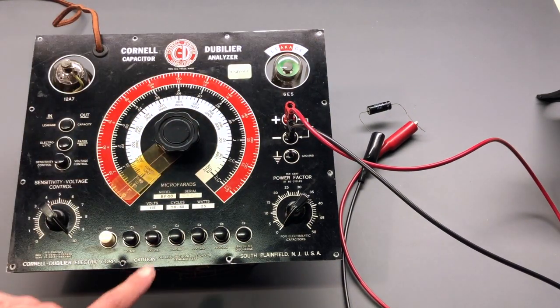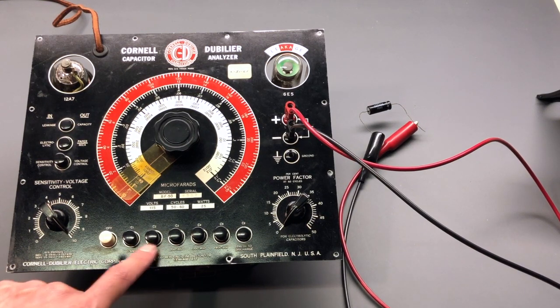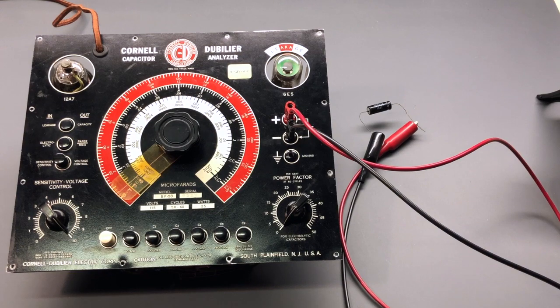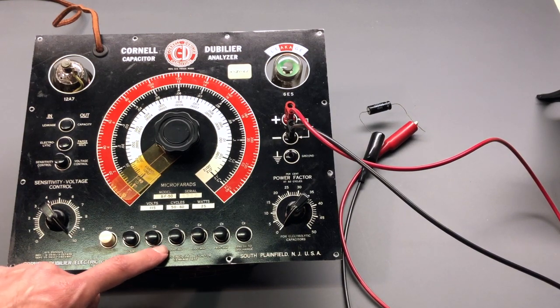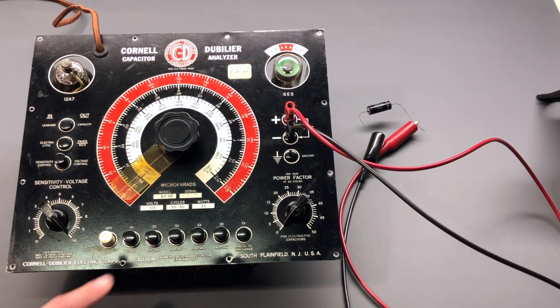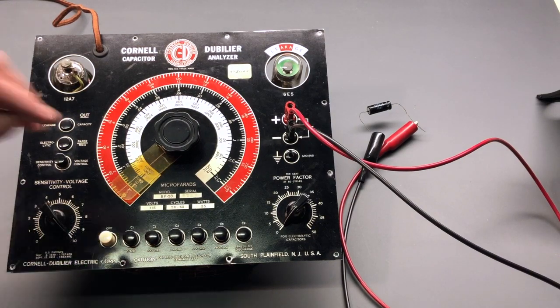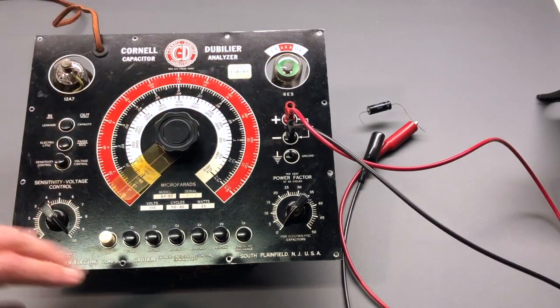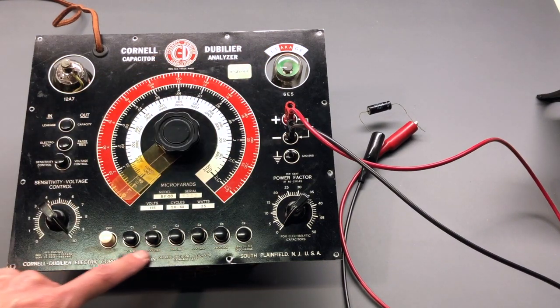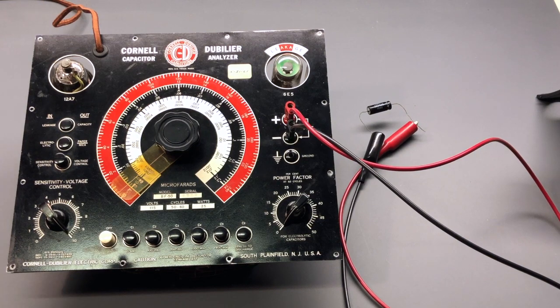This is a 300 volt capacitor, so I'll select the 100 to 200 range just to start with, and we'll see how it functions on that voltage range. You can select lower ranges, but really to check the capacitor in what you would consider a real world condition, you want to apply the voltage that approaches its rated maximum. If you apply a very, very low voltage, it would perhaps appear that the capacitor is okay and has low leakage current, but you're just simply not applying enough voltage to correctly test the capacitor. So again, you want to apply near its maximum voltage. And again, I'll connect the multimeter to these test jacks, and we'll see what the voltage is during this test, and see how accurate it is and how it compares to these ranges down here with an actual capacitor connected.